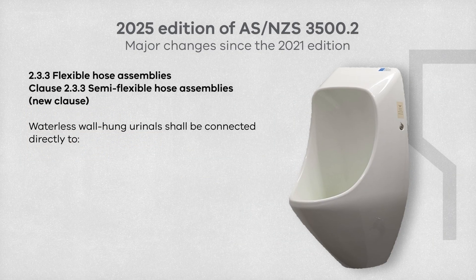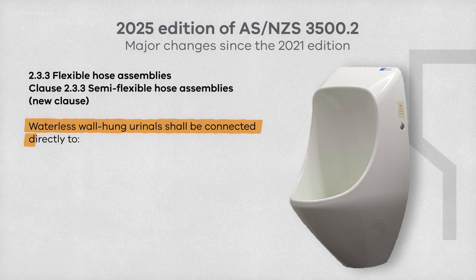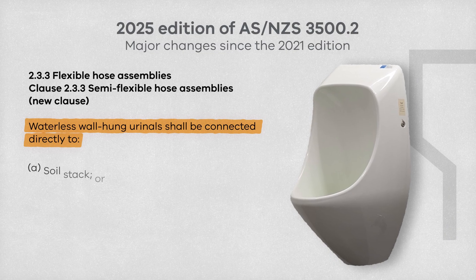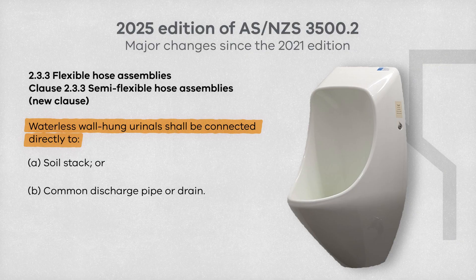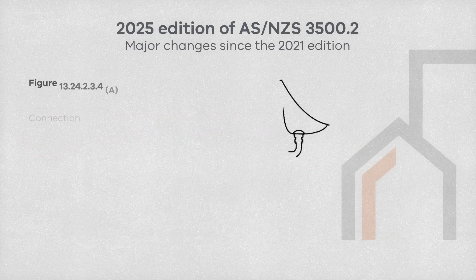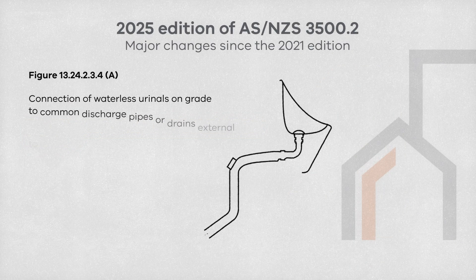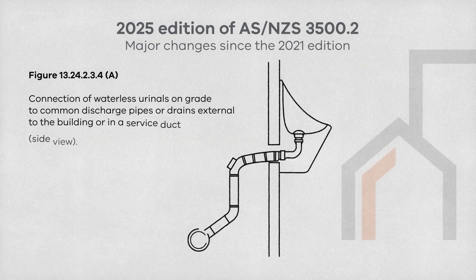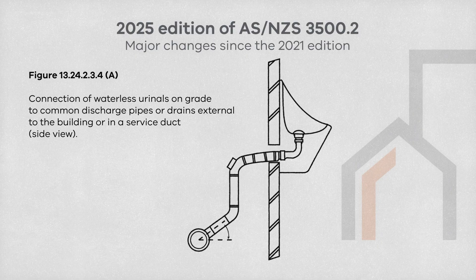In this new clause, it states that waterless wall hung urinals must be connected directly to a soil stack, common discharge pipe, or drain. A new figure has been introduced illustrating the connection of waterless urinals installed on grade to drains located outside the building or within a service duct, shown from the side view.